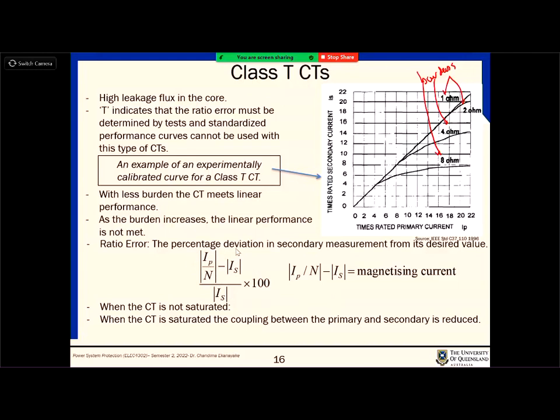So this is basically the magnetization current. IP divided by N minus IS is the magnetization current. That is divided by the secondary current and multiplied by 100 to give you the percentage ratio error. So if you look at this curve, you can find the corresponding error for different points. And also the ratio error, which is defined when the CT is not saturated.